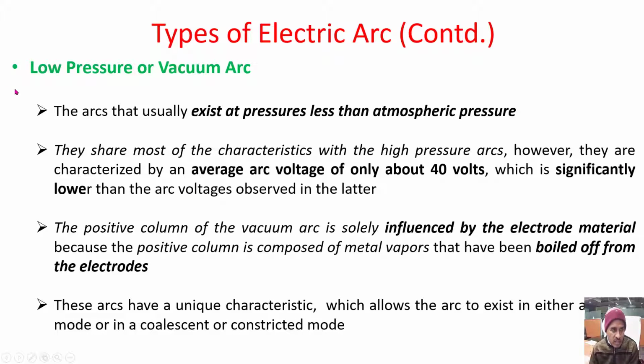Now, the second case is low pressure or vacuum arc. It's also called vacuum arc. So, the arcs that usually exist at pressure less than atmospheric pressure, for example, in a vacuum circuit breaker. They share most of the characteristics with the high pressure arcs, but they are characterized by an average arc voltage of just about 40 volts, which is significantly lower than the arc voltages observed in the latter.